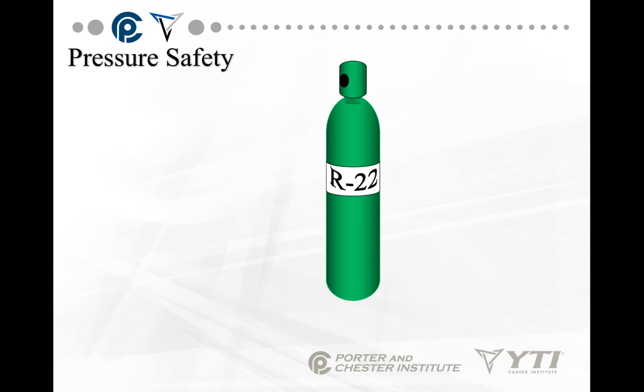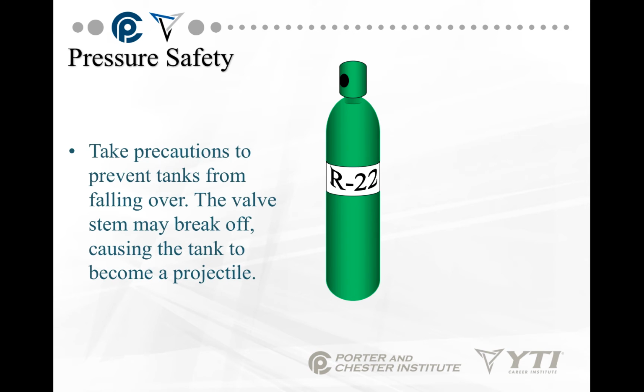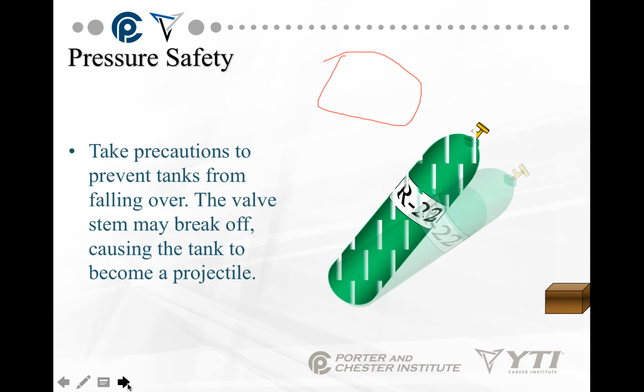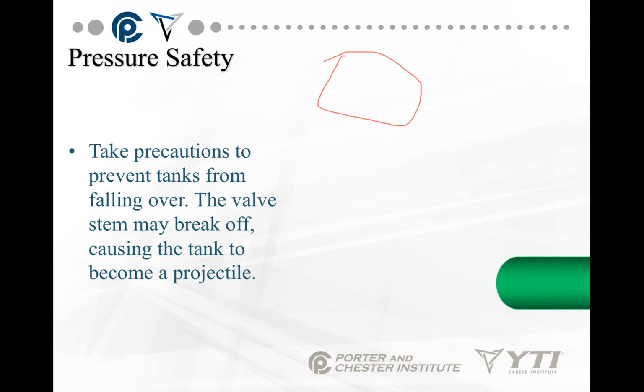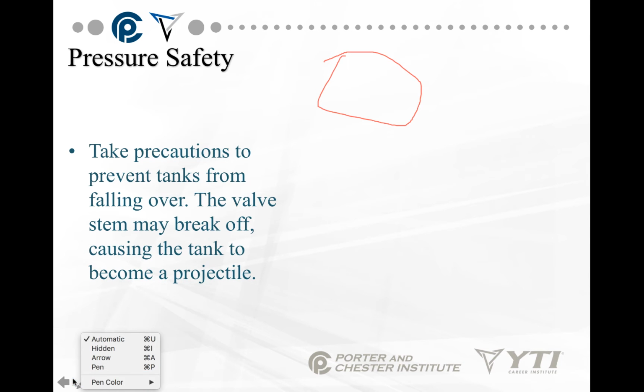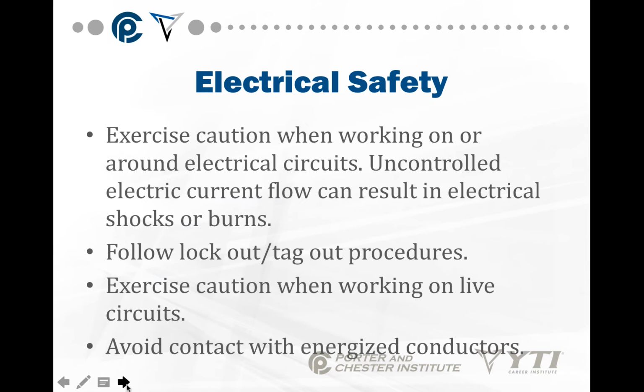Okay, so here we're talking about an R22 cylinder. R22 is one of the types of refrigerants that you will use during the course of this term. And we want to make sure that tanks don't fall over. The problem is not necessarily the tank itself. The problem is with the valve cover, the valve stem which is under this protective cover. As the tank falls over, that cover can actually knock itself off, and that tank can become an airborne container, almost like a rocket.